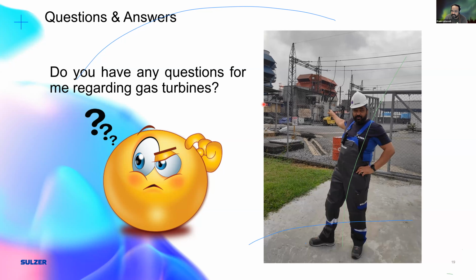For the old machines there are some exceptions - those built before a certain time are still allowed to run with higher limits, but newer ones have to comply. So additional systems come in, like a purge water system, to create an emulsion that reduces the effects of the NOx. Or you can have post-gas treatment where ammonia is introduced to capture some of the NOx. So there are different systems in place.